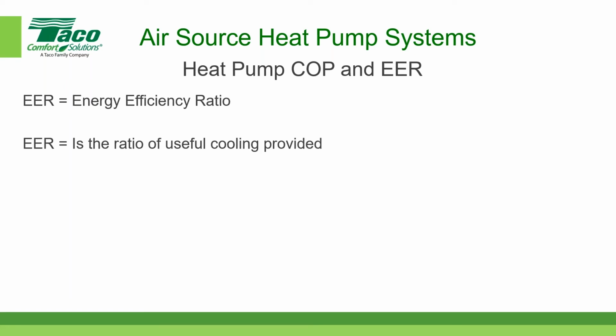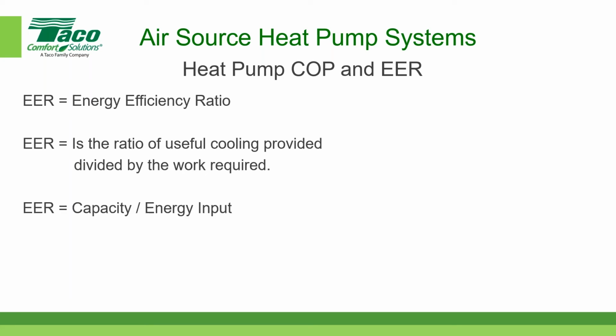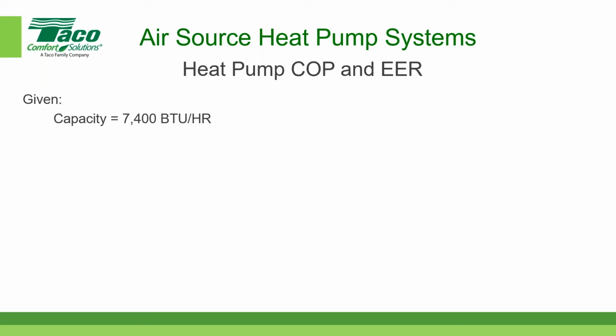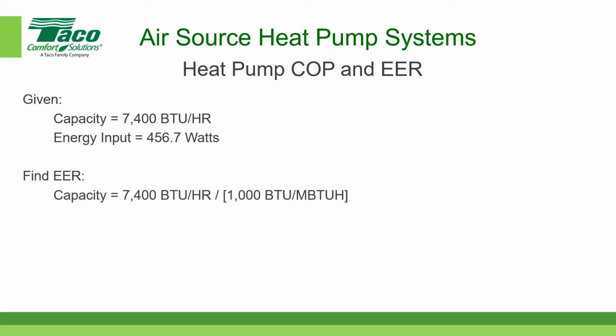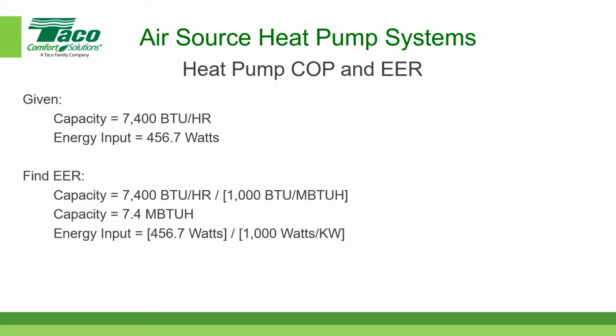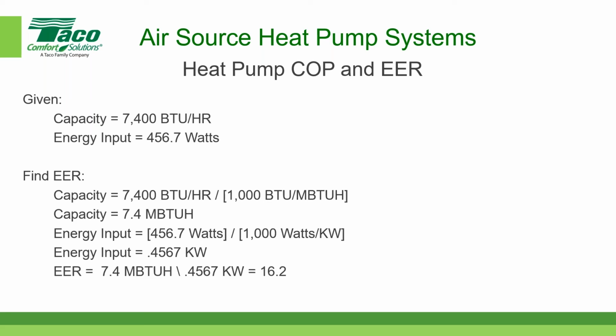So in other words, it's the ratio of useful cooling provided divided by the work required, the same exact concept as before. The capacity, however, is in BTUs per hour, and the energy input is in kW. So if we give 7,400 BTUs per hour, and we have an energy input of 456.7 watts, the EER is 7,400 divided by 1,000, because we want to convert it into thousands of BTUs per hour, and that's 7.4 MBTUH. The energy input is in kW, so simply divide that by 1,000. Now you divide 7.4 by 0.4567. It comes out to 16.2.